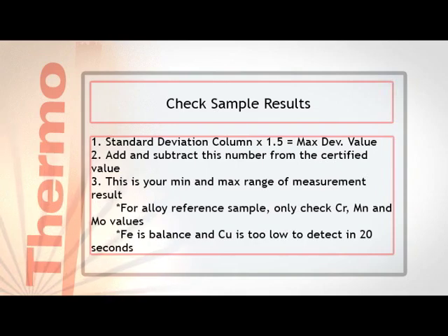By close we mean, if you multiply your standard deviation by 1 1/2, this will give you your maximum deviation value. You will then add and subtract this number from your certified value. This is your minimum and maximum range of measurement result. For alloy reference samples, you will only check the chrome, manganese, and moly values. We do not verify iron since it is only specified as the balance.